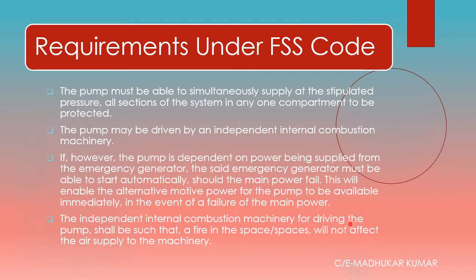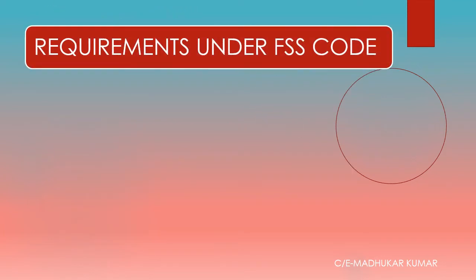If an independent internal combustion engine is used to drive the pump, fire in the protected space must not affect the air supply of the engine. The system installation should be located outside machinery spaces. This ensures the IC engine air supply is not affected by a fire in the machinery space.